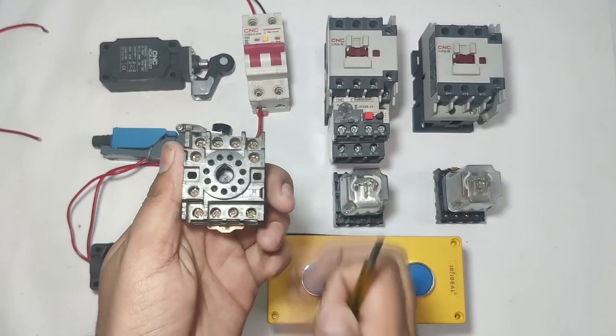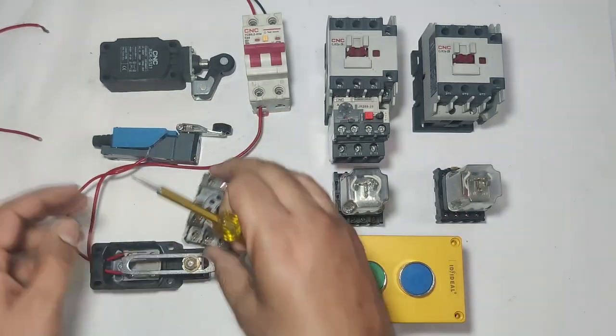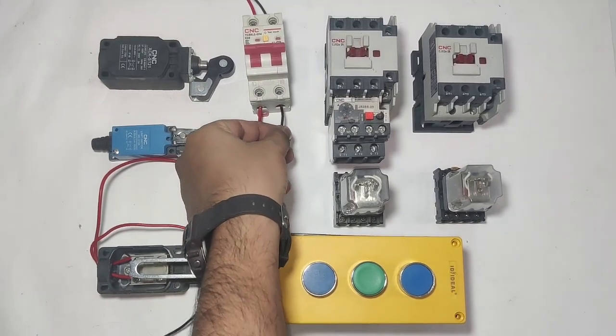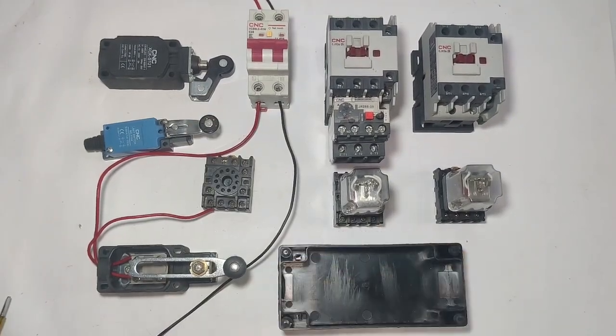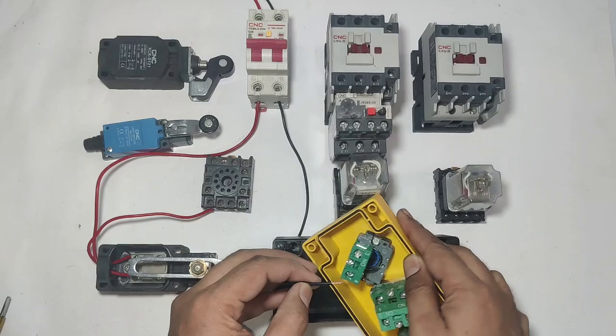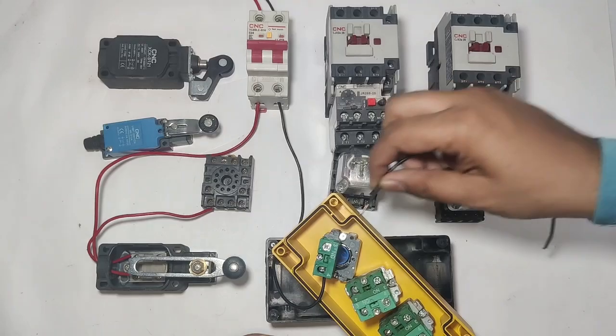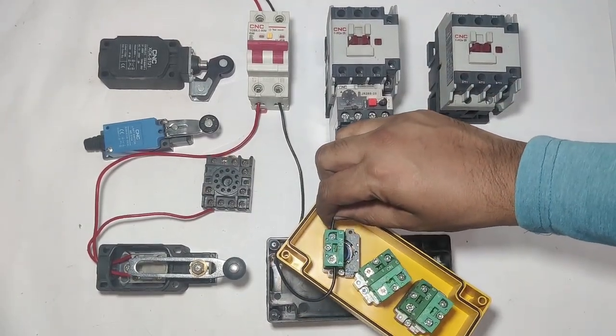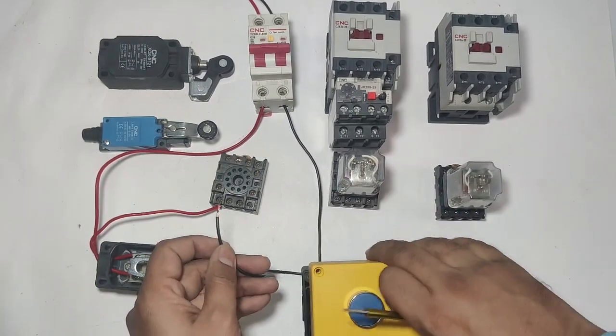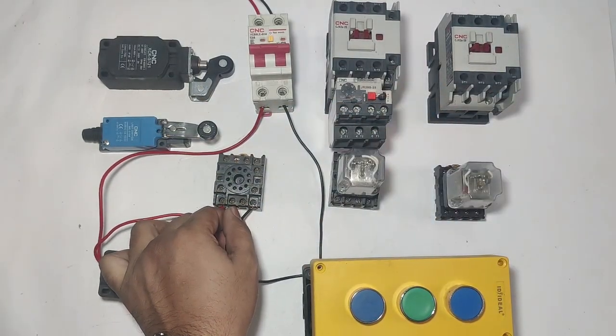Check the limit switch: common, NO, and NC point. The NC output connects to the relay. This is an 11-pin relay — pins 2 and 10 are the relay coil, so we connect to pin 10. Line connects from the limit switch NC. Neutral connects first to the push button of the ground floor NO point. When this NO element operates, supply comes into relay pin 2 and the relay operates.